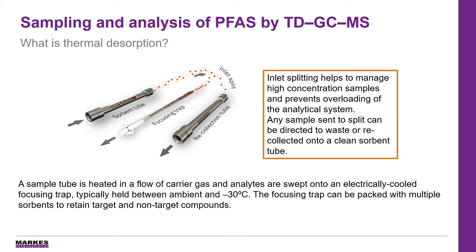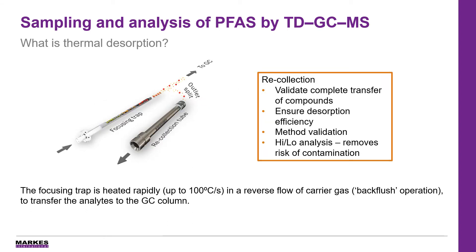For this study we used an off-the-shelf focusing trap typically used for air monitoring applications. Subsequent rapid heating of the TD instrument's internal focusing trap in a reverse flow of carrier gas transfers the volatile and semi-volatile organic compounds to the GC column in a narrow band, and this is what ensures those sharp peaks and a high level of sensitivity. This back-flush operation of the tubes and the traps makes elimination of water via dry purge procedure an extremely effective water management tool, which improves sensitivity and extends instrument and column lifetime.